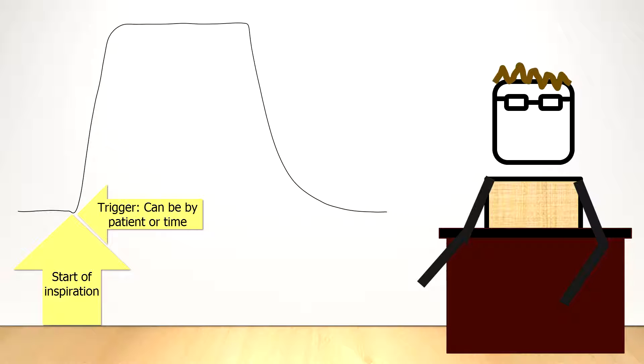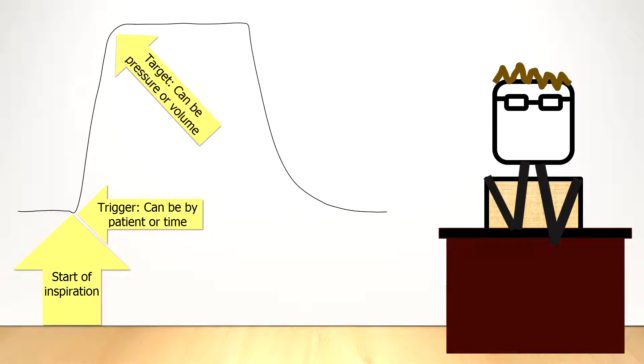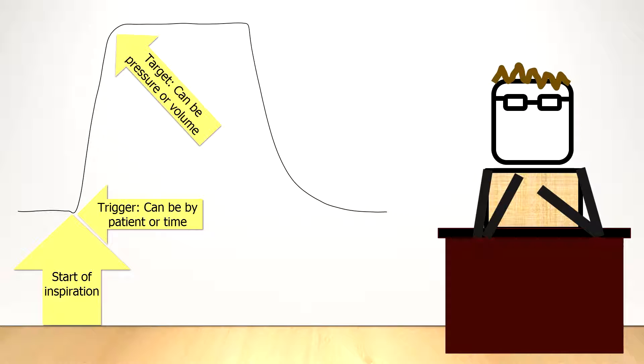The next phase of the ventilator cycle is the target. The target is simply the set pressure or volume that you determined to be the control mode for the ventilator. If you set the ventilator to a certain number of milliliters of volume, then the target is when the ventilator reaches that total volume to be delivered.